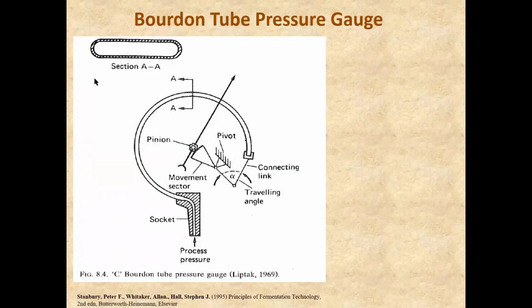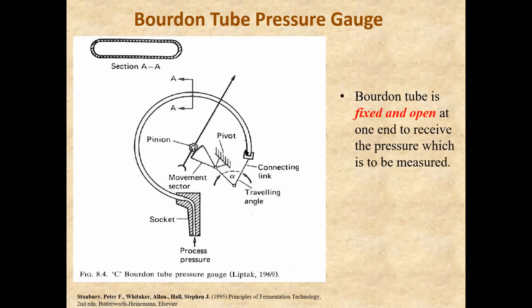The partial coil has an elliptical cross section which tends to become circular with increasing pressure, and because of the difference between the internal and external radii, it gradually straightens out. Now, if you see this C-type Bourdon tube in this picture, it has two ends. This is one end and this is the other end. The one end of the Bourdon tube is fixed and open.